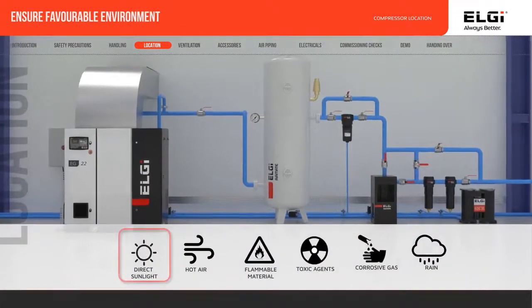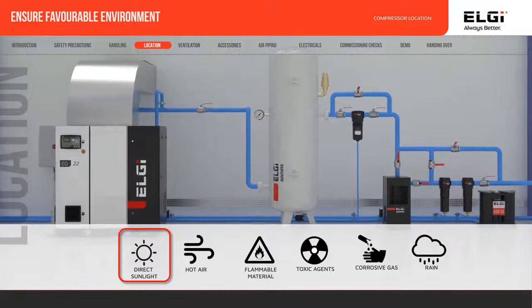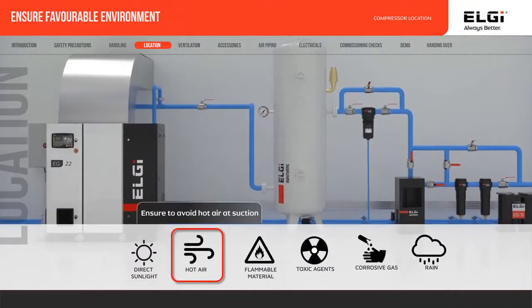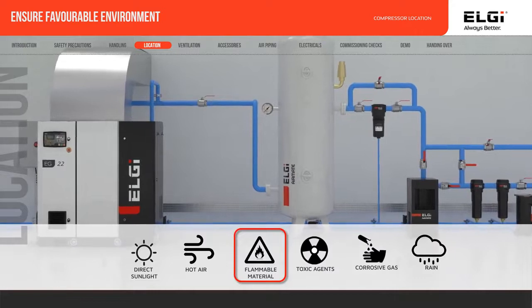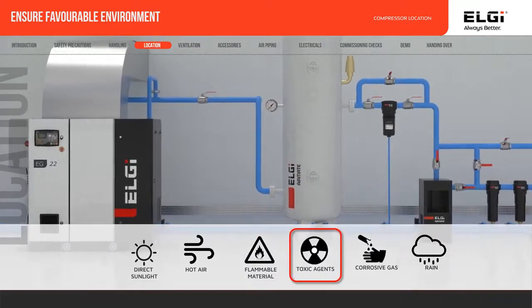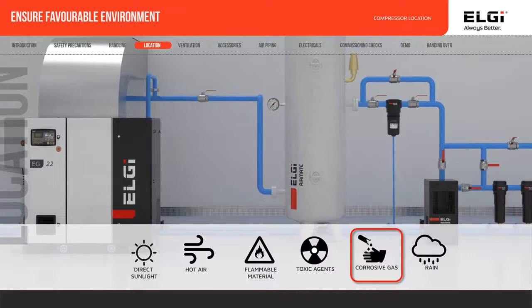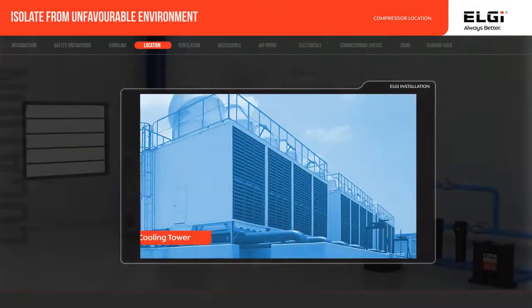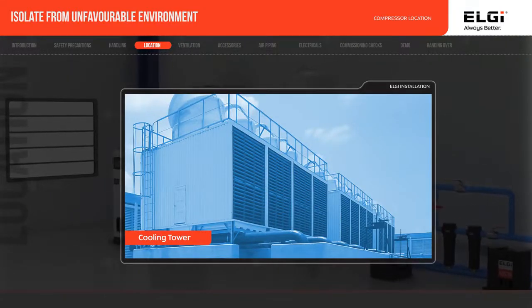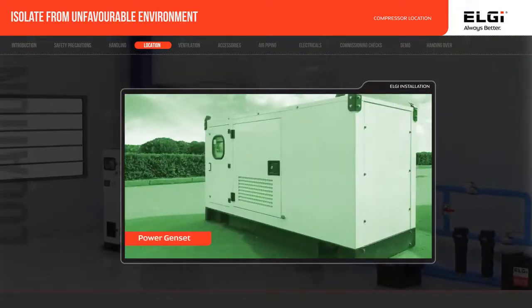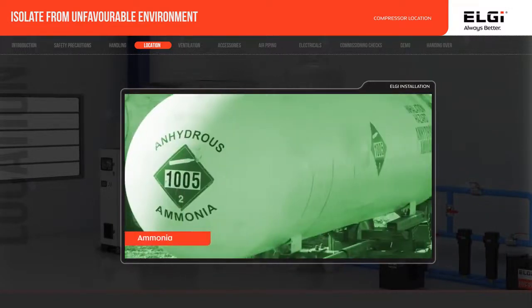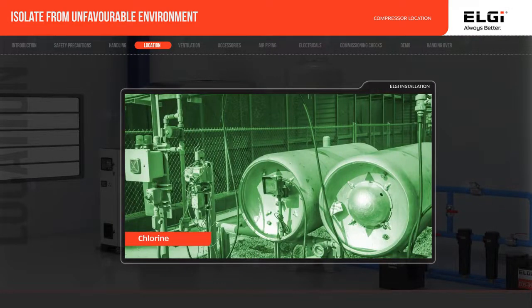Ensure that the compressor is protected from direct sunlight, hot air, flammable materials, toxic, volatile or corrosive agents, and rain. The compressor should not be directly exposed to water cooling tower, power genset and corrosive agents like ammonia, chlorine, salt spray and other chemicals, as these may erode the internal components and also contaminate the oil, and affect the filters.